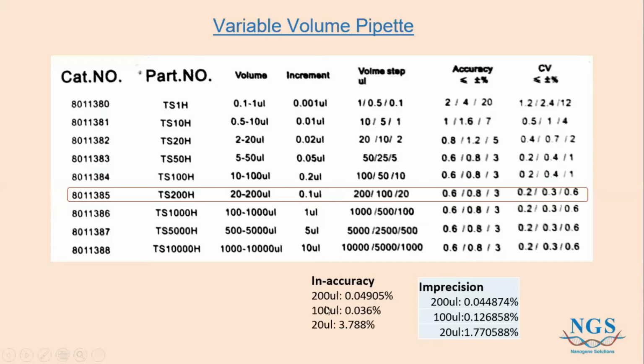My value is 0.04%. I look at the table that my manufacturer gave me, and if my pipette is valid, the accuracy range should be within positive 0.6 to negative 0.6%. If my value is within that range, my pipette is still good and I don't really need to calibrate it. I'll give you 5 seconds to think about whether my value is actually within the range.